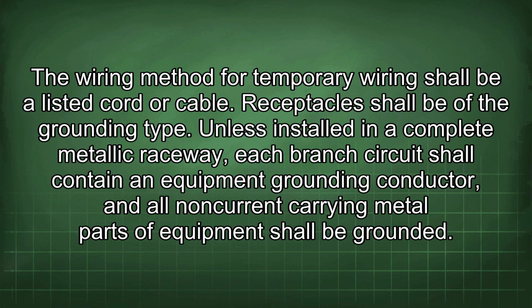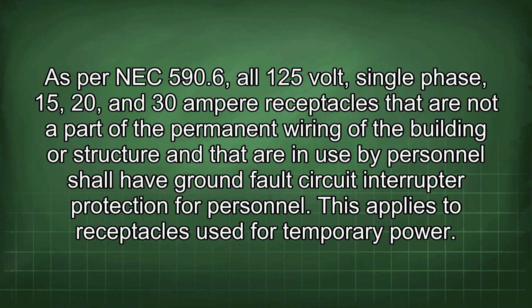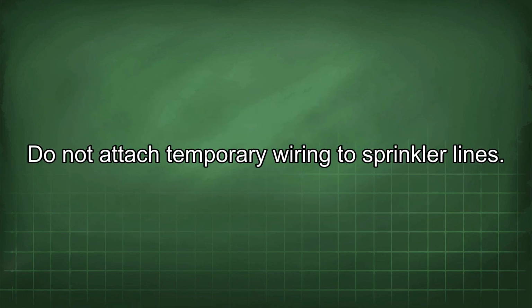Receptacles shall be of the grounding type. Unless installed in a complete metallic raceway, each branch circuit shall contain an equipment grounding conductor, and all non-current carrying metal parts of equipment shall be grounded. As per NEC 590.6, all 125-volt single-phase 15, 20, and 30 ampere receptacles that are not a part of the permanent wiring of the building or structure and that are in use by personnel shall have ground fault circuit interrupter protection for personnel. This applies to receptacles used for temporary power. Do not attach temporary wiring to sprinkler lines.